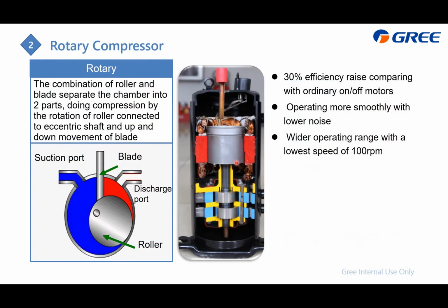And just like what I have said, the inside compressor is an inverter. We adopt it from our developer. It is rotary, and how it works is just like this. You can find the rotor here. When it runs, it will just compress. Also, compared with the regular on-off, the efficiency is extremely high. This is very helpful, with very high performance especially in low load conditions, because we can lower the compressor output to meet the load. And later I will display the performance test results.